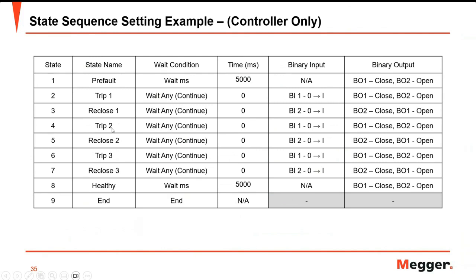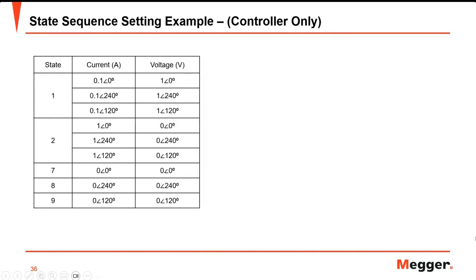The states from four onwards cover up to the third shot — this is set for three shots. If you want to check the lockout or until the relay sends a lockout command, you can add more states. These are some examples of the test values; these values may change depending on the protection functions you are testing. If you are testing other protection functions that need voltage, you can put the voltage values here — it depends on the functions you want to test.